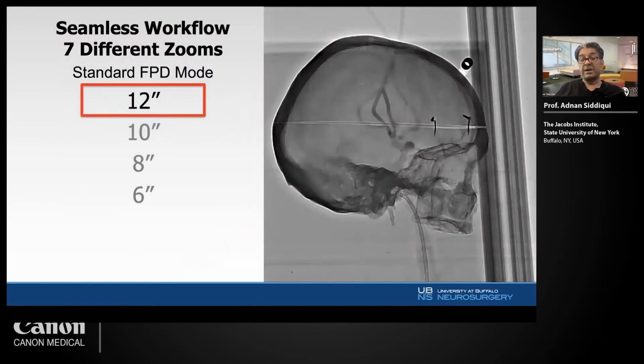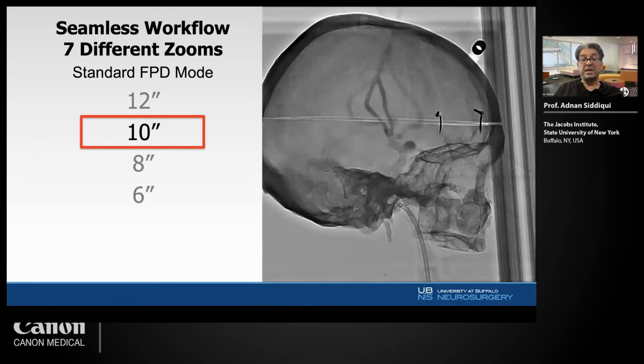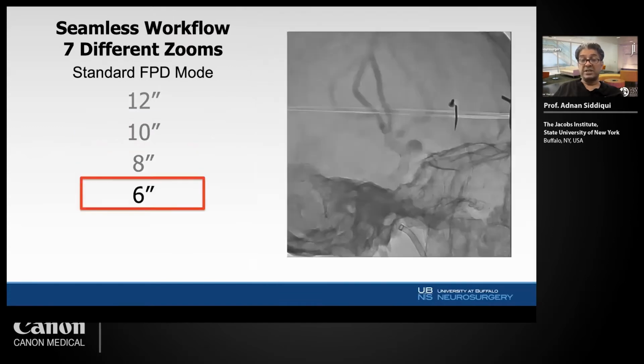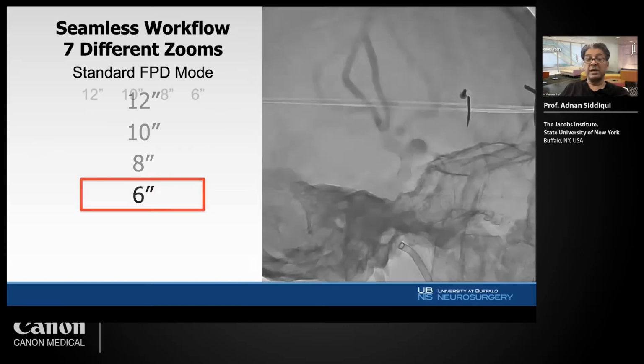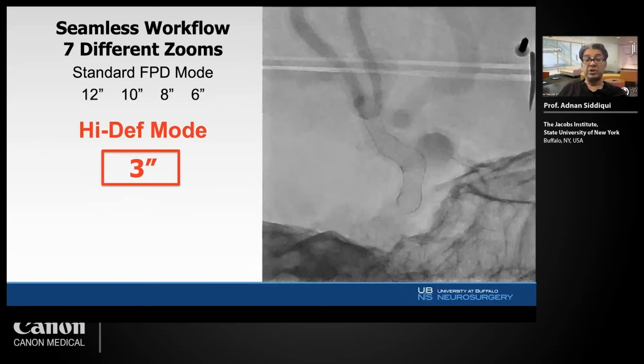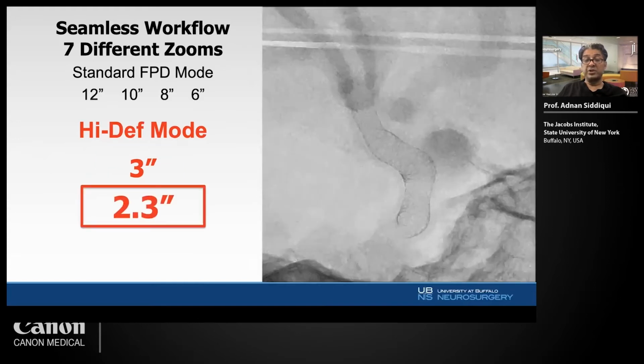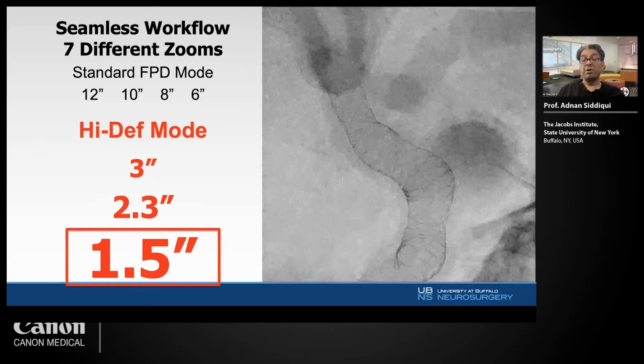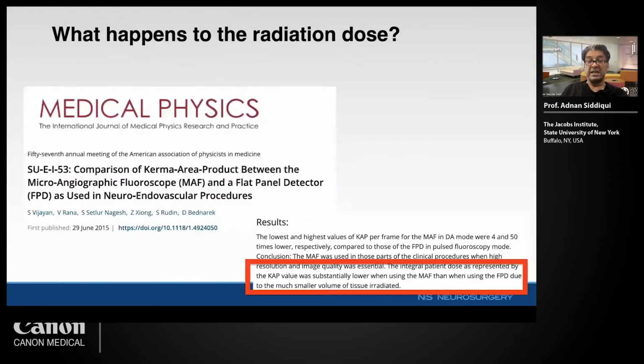This is a standard flat panel detection of lateral fluoro, and this shows you as we go from 12 to 10 to 8 to 6 inches. That's the end of flat panel, and this is where we go into a 3-inch and then 2.3 inch. And then this is what's currently available, a 1.5 inch. So you can imagine the kind of detail one can arrive at, where you are seeing the platinum wires, and you're literally even seeing the chromium cobalt in there. You can see the compression of the device here and a little bit more relaxing out here and out here. So it really allows you to visualize the device like never before.